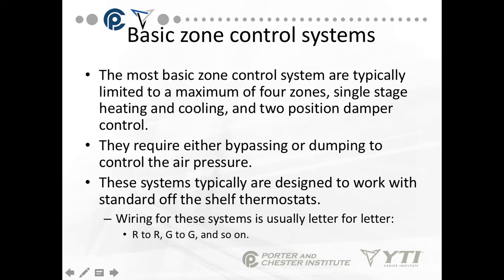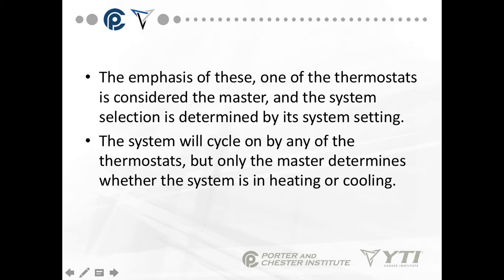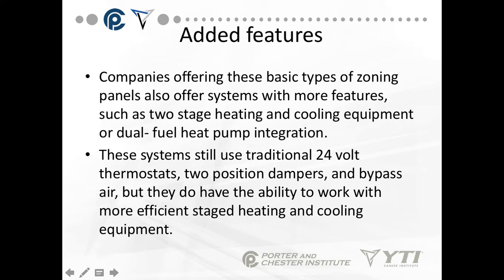Wiring for these thermostats is usually letter for letter — R to R, G for G, and so on. One of the thermostats is considered a master, and the system selection is determined by its system setting: whether the system is going to be in heating or cooling, fan-on or fan-auto. The system will cycle on by any of the thermostats, but only the master determines whether the system is in a heating or cooling mode.